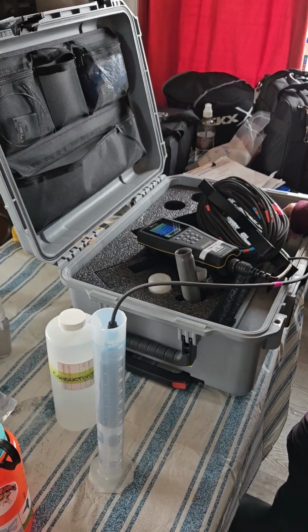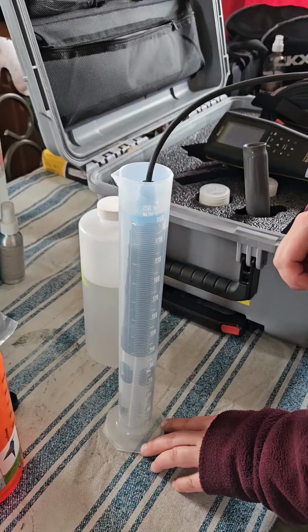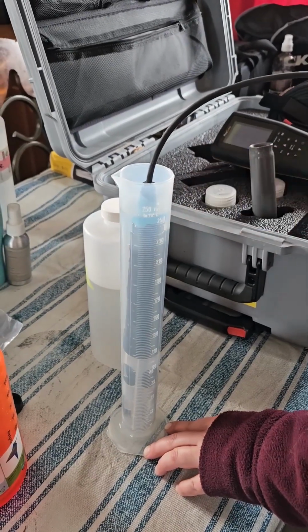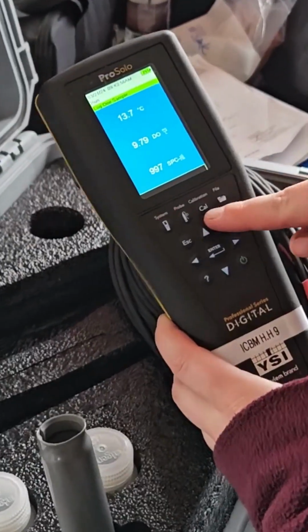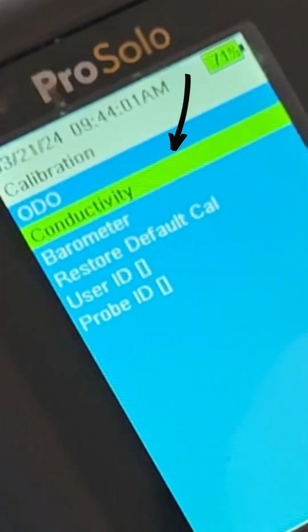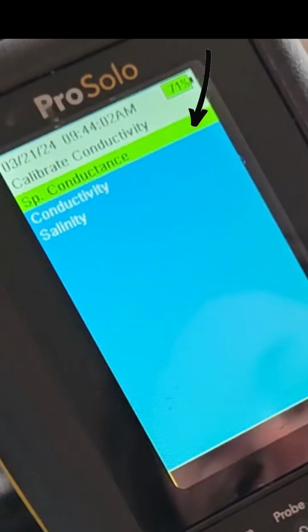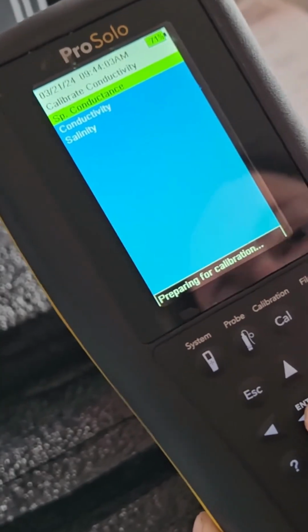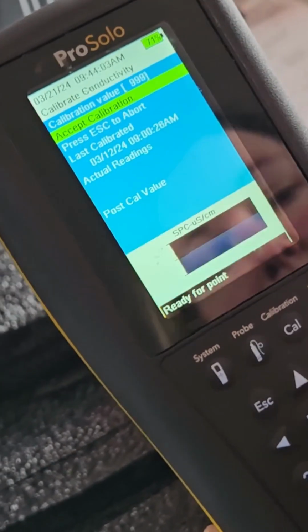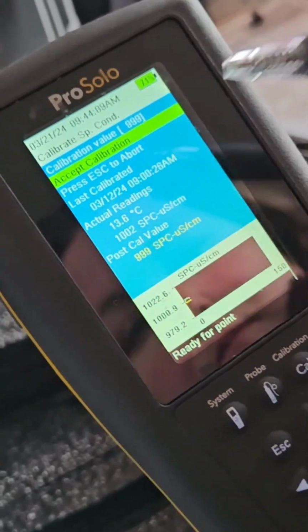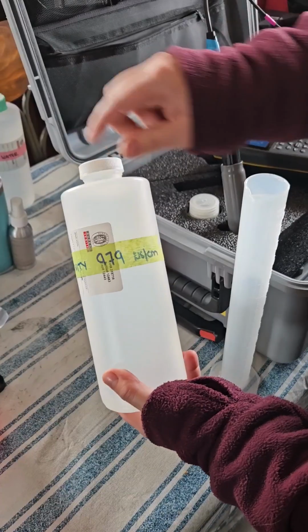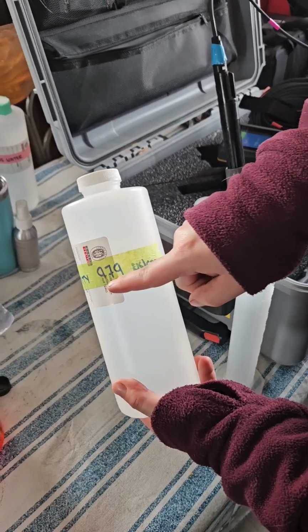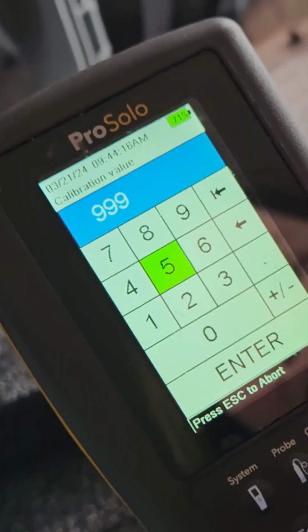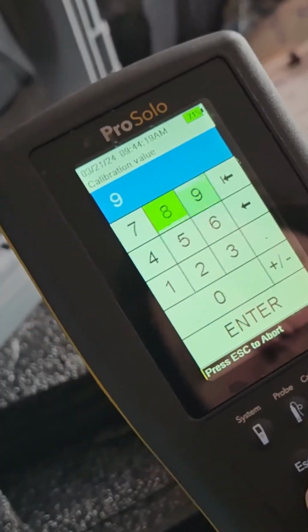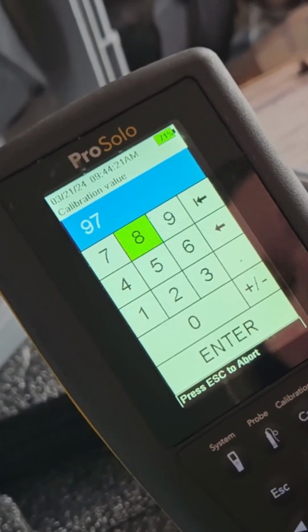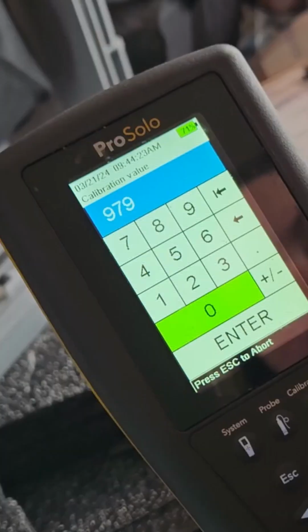Once that's completed and we're making sure that there's no air bubbles, we will go to our handheld and press calibration, this time looking for conductivity, enter. We'll click on specific conductance, and then we will be at our screen again, and we will click on the calibration value, and we're going to change that to those numbers that are written on the calibration solution bottle. So for here, it's 979. We'll enter, and then we'll see that calibration is beginning.